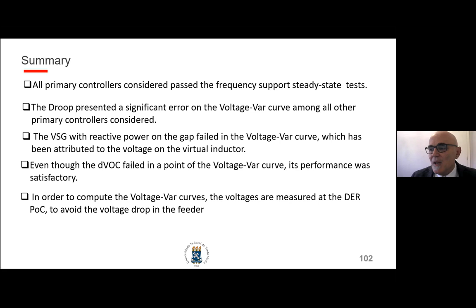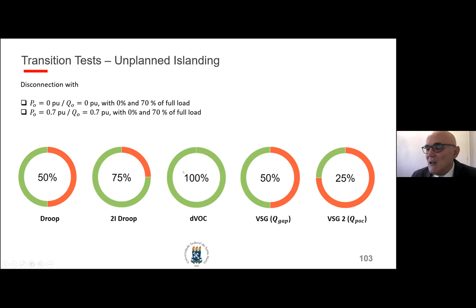Okay, so the transition test over here is the unplanned island. Here we assume that there is a delay between the secondary controller and the primary controller of the different DERs, and the results depend on the set points. So we consider different set points for the active and reactive power. We also consider that the microgrid has different loads from 0 to 70% of full load. From this result, we see that DVOC gives the best performance.